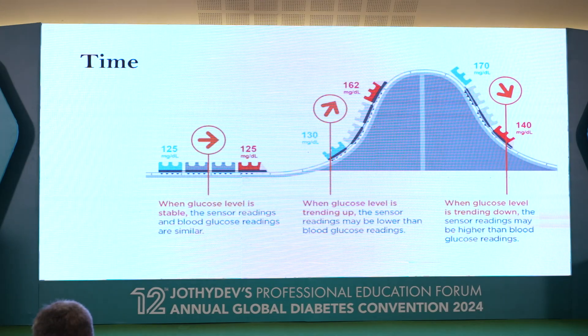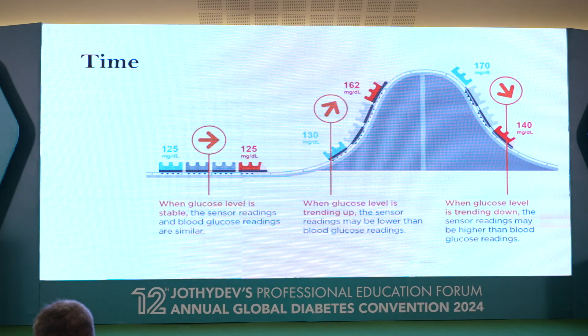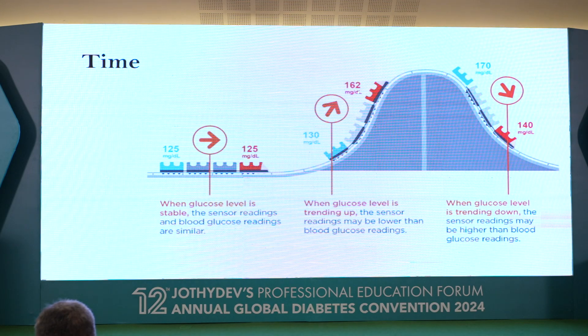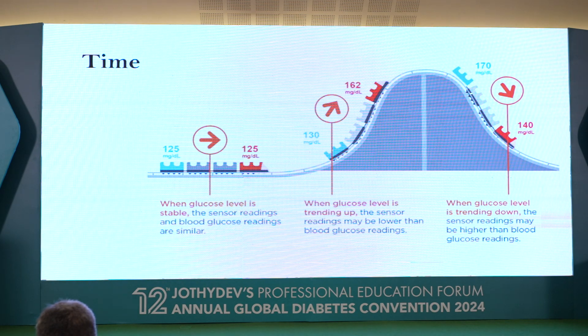Another important concept is time lag. As mentioned earlier, interstitial fluid glucose lags behind capillary glucose — there is a time lag of 8 to 10 minutes, which we should be aware of. This is particularly important when there is a rapid fluctuation in sugar levels, whether rising or falling very fast. When sugar levels are rising rapidly in the capillaries, the interstitial fluid may lag behind and not reflect the true value correctly. Similarly when falling rapidly, you may not capture it accurately in the CGM device. So when levels are changing rapidly, be aware of the time lag.